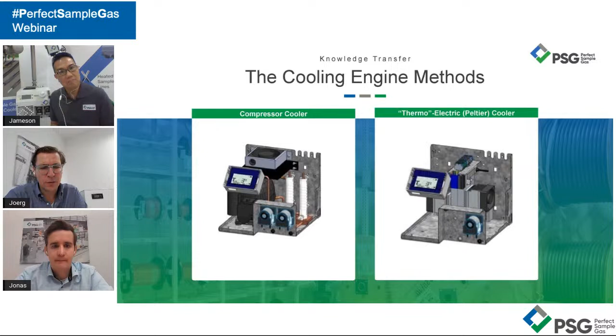Jameson, from your experience, what would you say is the more common cooling technology in your region? In my region, generally we use compressor coolers. The reason is that both can reach the same dew point. However, there are two factors I always stress to my partners. Number one, look at the energy, the amount of BTU, how strong and powerful this gas cooler is able to squeeze out the water. This is very important.